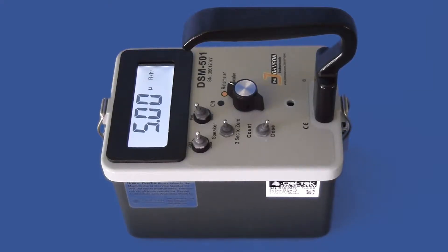This video shows you how to operate the DSM-501 microroentgen meter. This meter is used to survey gamma and x-ray at the microroentgen level. The range is 1 microroentgen per hour to 10 milliroentgen per hour.